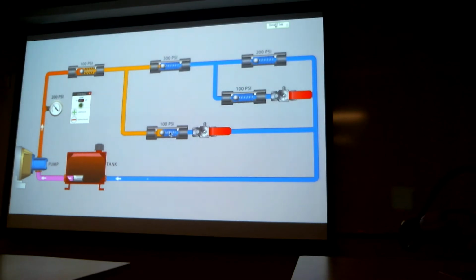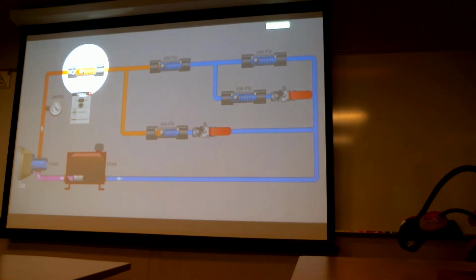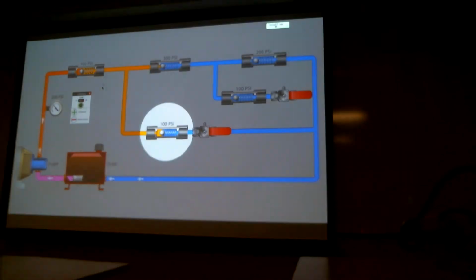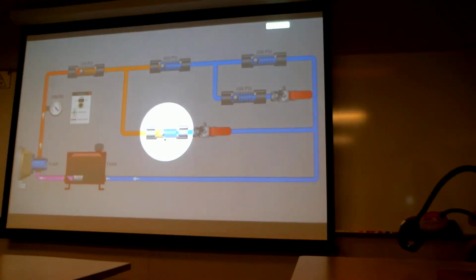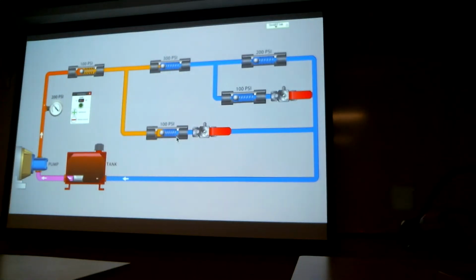As you know from earlier videos, the system pressure reflects the easiest path that the pump's flow could take. We've got 100 psi on the first spring-loaded check valve and another 100 psi spring-loaded check valve downstream. So those two loads add together to give us our system pressure.